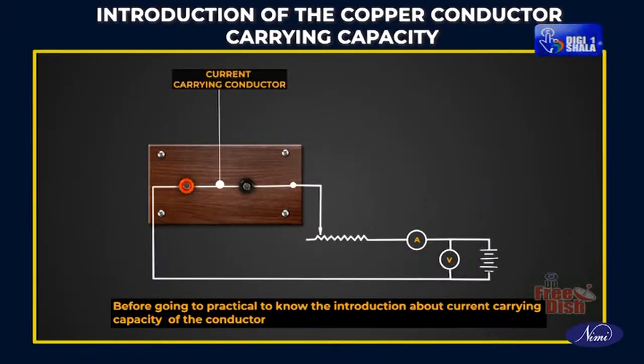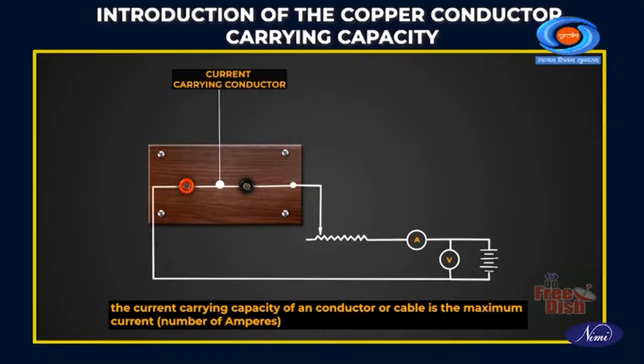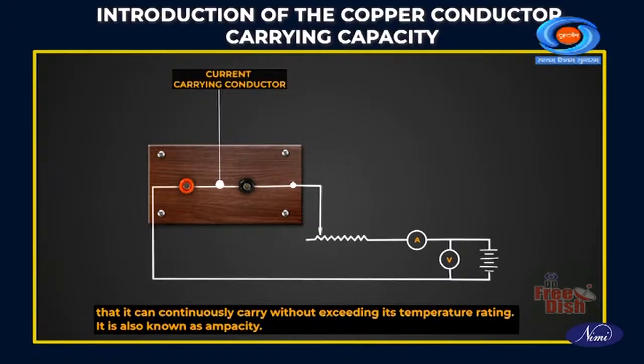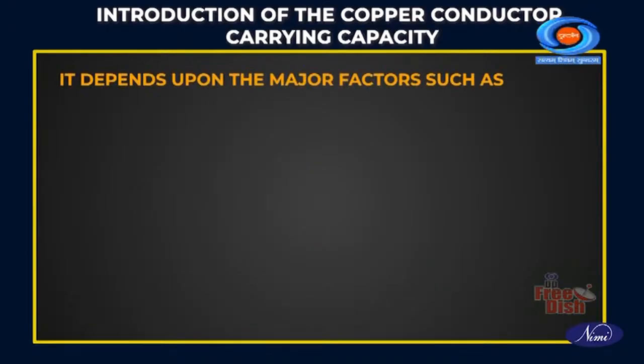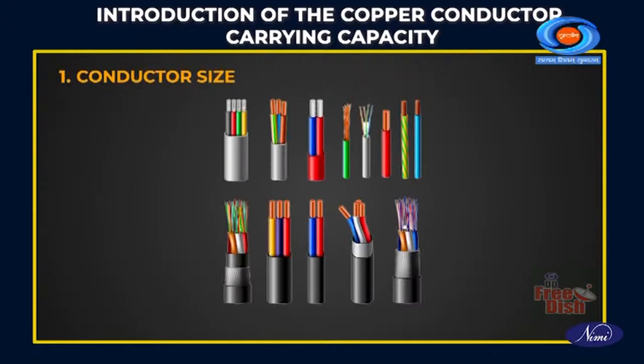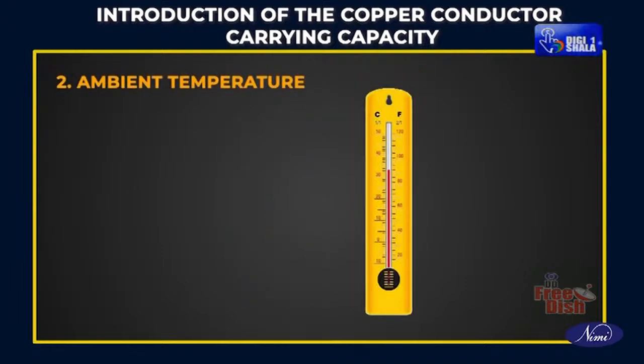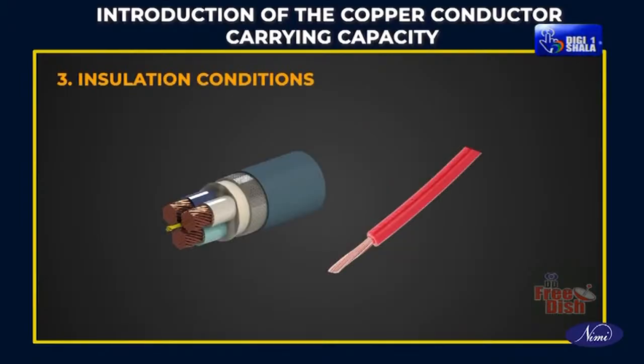Before going to the practical, here is an introduction to the current carrying capacity of a conductor. The current carrying capacity of a conductor or cable is the maximum current, that is, the number of amperes that it can continuously carry without exceeding its temperature rating. It is also known as ampacity. It depends upon major factors such as conductor size, ambient temperature, and insulation conditions.